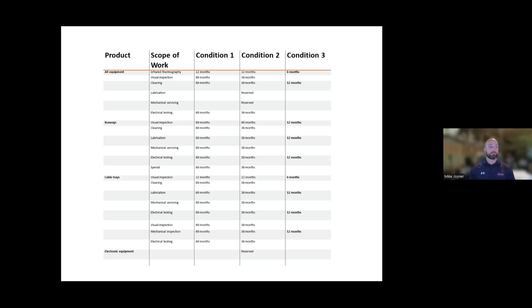Based off of 9.2.2, when we do these shutdowns, there are other tables that tell us exactly how to properly maintain the conditions of the maintenance of the equipment. In here, there's molded case breakers, insulated-case circuit breakers, low voltage breakers, as well as the medium voltage breakers. The following table that we're going to dive into basically talks about how and at what frequency we have to work on these pieces of equipment.